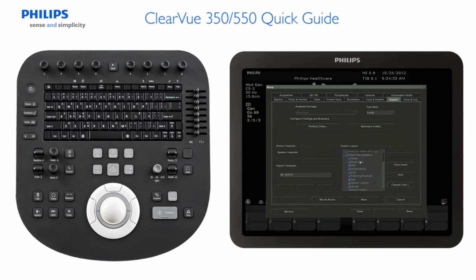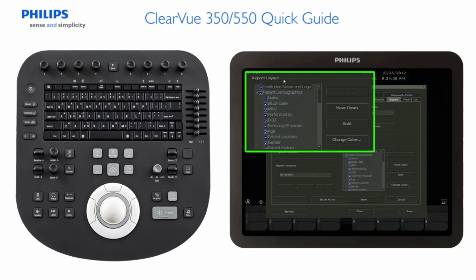There are several options to customize the report. For example, in the Report Layout window, the header fields and many of the subheaders can be set in bold. You can arrange a sequence of header fields in the report layout by selecting the word in the field header to highlight it and then click Move Up or Move Down. The report layout for each analysis type is composed of a section header and subheader information fields. The header fields associated with the plus sign contain editable content. To open the content of the header field, place the pointer area over the plus sign and press the left or right trackball.